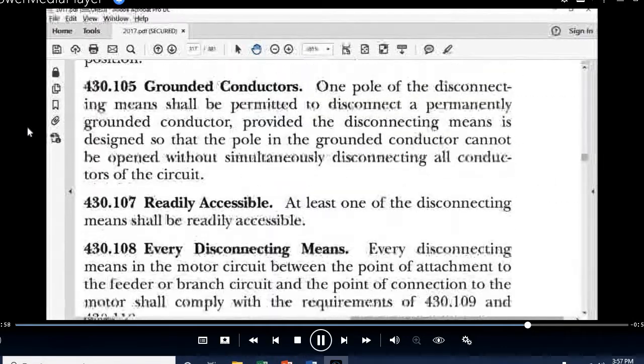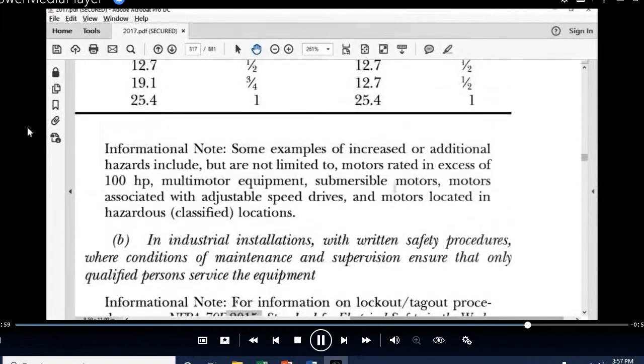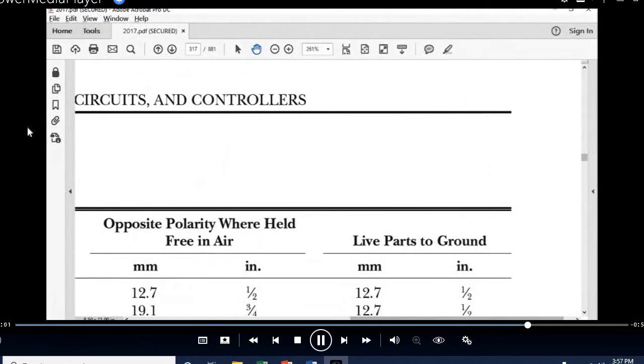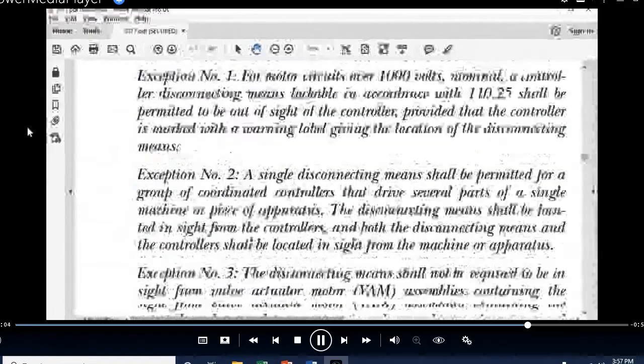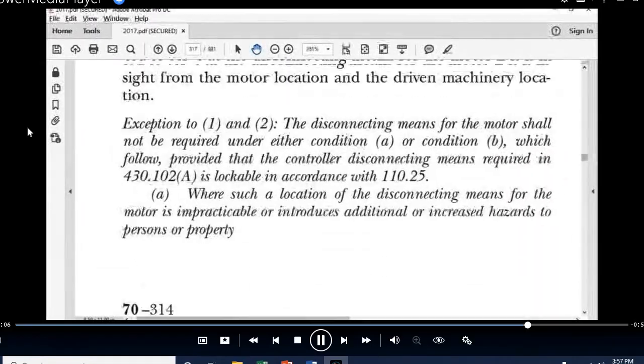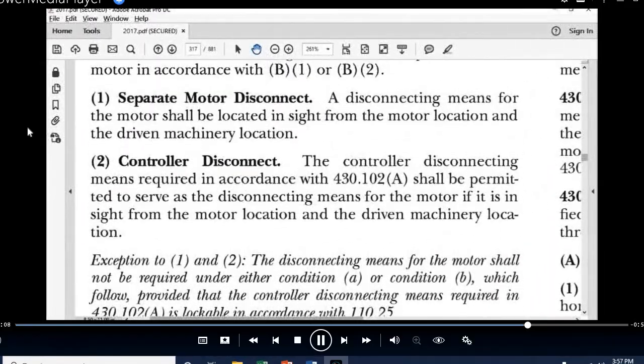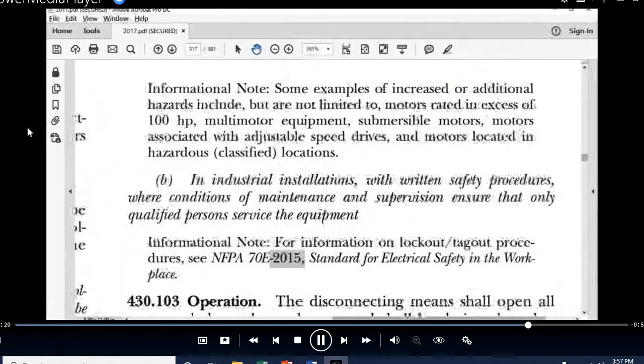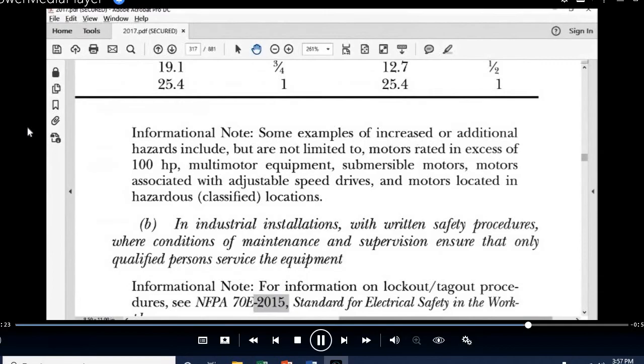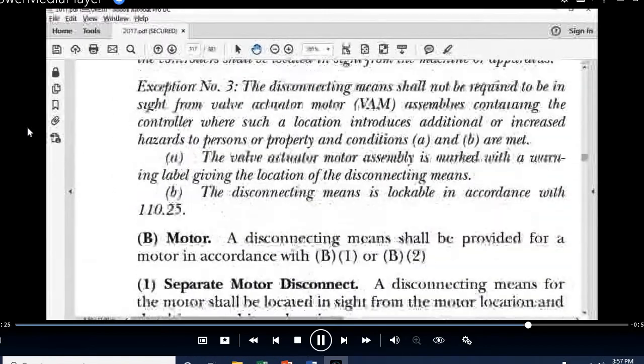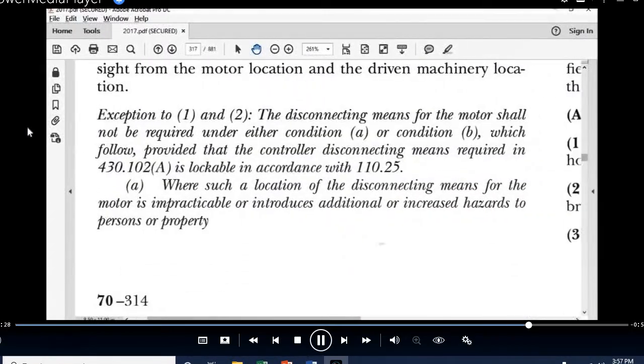Let's go over to the motor disconnect. All right, let's go here. A disconnecting means for a motor shall be located within sight of the motor and the driven machinery. The controller disconnect is permitted to serve as the disconnecting means for the motor if it's within sight. Then we have an exception for the motor disconnect, and here's what it says. I skipped it, didn't I? The controller disconnect exceptions, yeah.